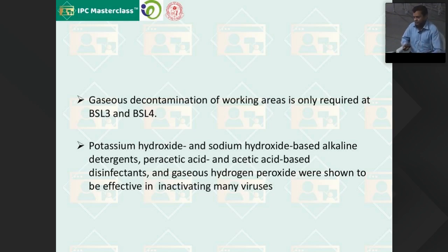We have seen in many labs, and I don't want to elaborate here, air handling units are left like that. There is no proper air handling unit. Ducts have been contaminated. HEPA filters have been used for more than 3 years. There was no validation of the HEPA filters. So these all defeat the purpose of the atmosphere you are trying to create inside. So all these things are important. It has to be decontaminated, and these chemicals can be used for the decontamination of your laboratories. Mostly they are high level disinfectants like sodium hydroxide, peracetic acid, and so on.